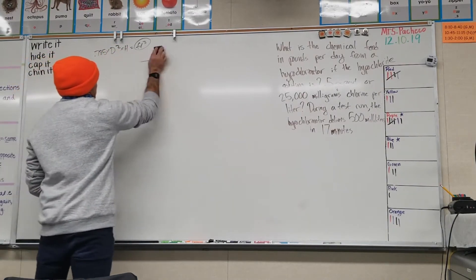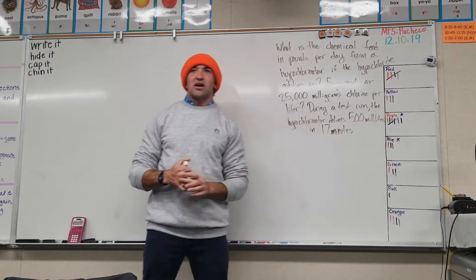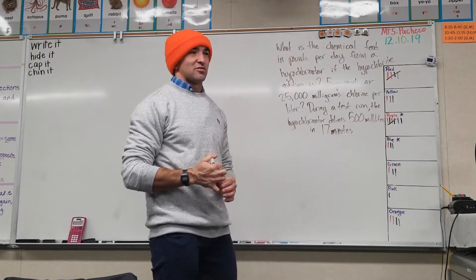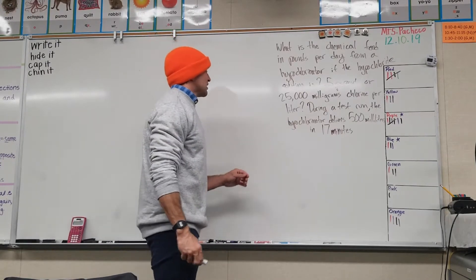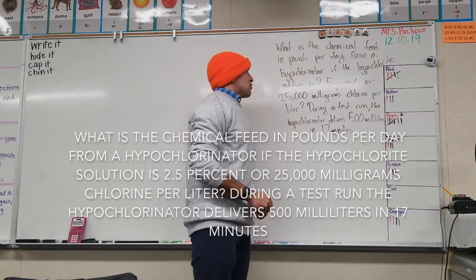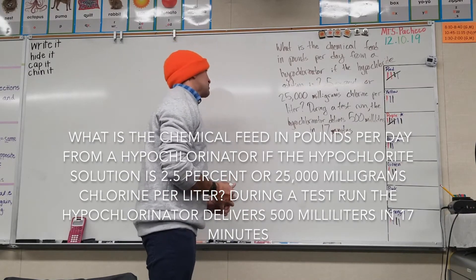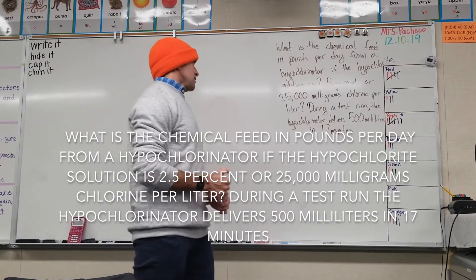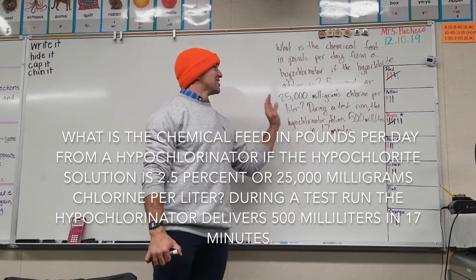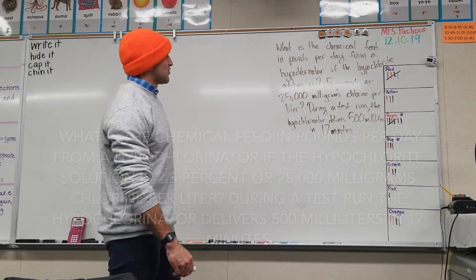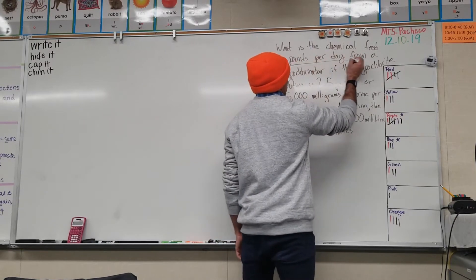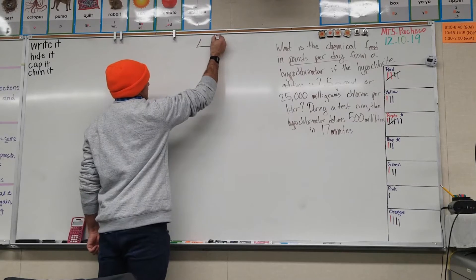Now we're adding another tool to the belt. The question is: what is the chemical feed in pounds per day from a hypochlorinator if the hypochlorite solution is 2.5 percent, or 25,000 milligrams of chlorine per liter? During a test run, the hypochlorinator delivers 500 milliliters in 17 minutes. What is the chemical feed in pounds per day?